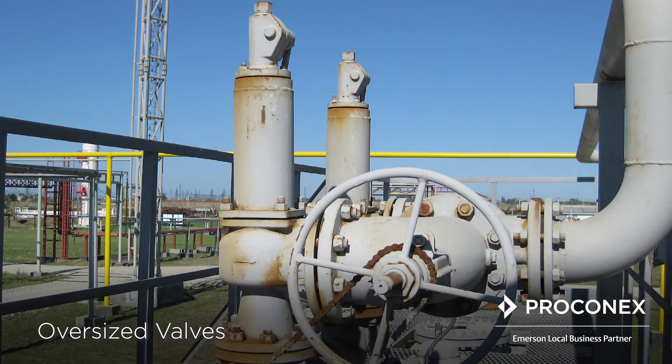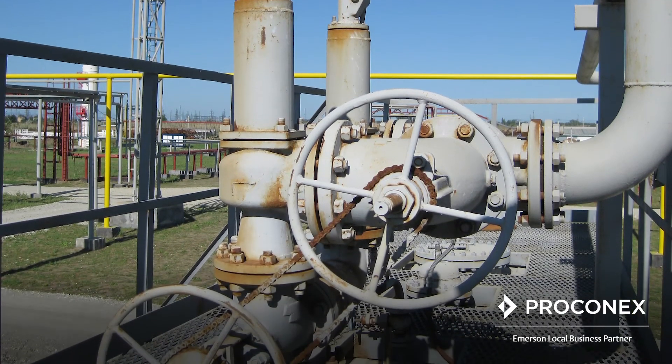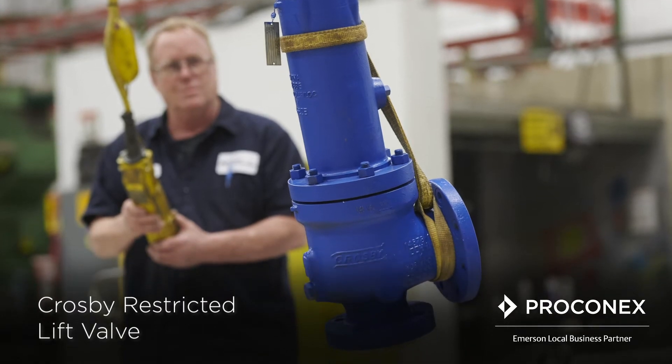The first scenario is oversized valves. An engineering firm may suggest a smaller valve, but that might not always be the best solution. Piping modifications can be costly and require a shutdown. Proconex offers a Crosby restricted lift valve that does the job at a lower cost without disruption. The valve meets the required capacity without requiring piping changes.